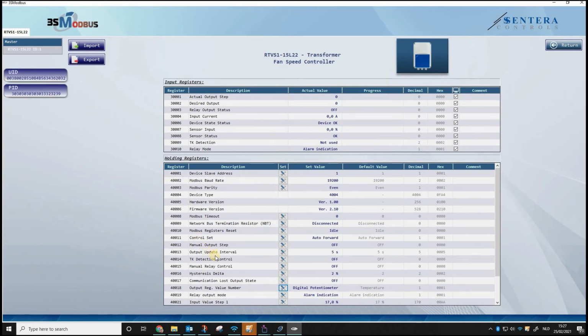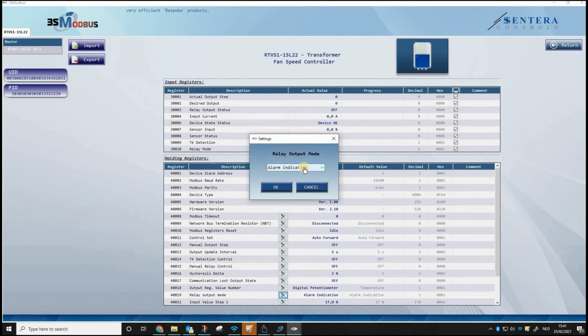However, I will show you what the relay should respond to. Via Modbus register 40019, you can choose whether the 230 volt non-regulated relay output will respond as soon as an alarm occurs, or that you're going to switch this output manually via Modbus register 40015, or that the 230 volt is applied to the output as soon as the unit switches to positions 1, 2, 3, 4, 5, or even the other way around, 230 volt is applied to the unregulated output when the unit is at 0 position.